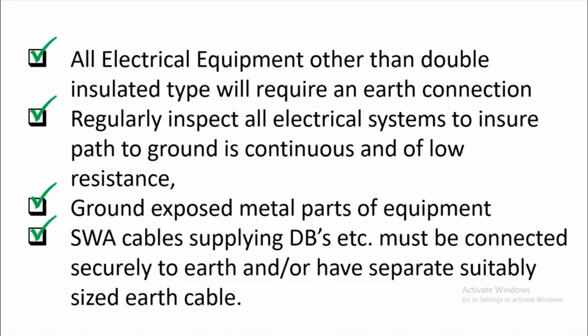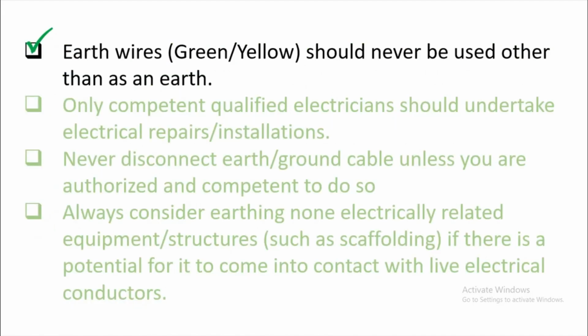All the exposed metal parts of the equipment should also be earthed or connected to the earth connections. Steel wire armored cables supplying distribution boards etc. must be connected securely to earth and/or have a separate suitably sized earth cable. So even if these are armored cables, they should be connected to the earth. Earth wires, green and yellow, should never be used other than as an earth. So remember, there is a color coding on electrical cables. You cannot use the green or green and yellow for any other purpose other than for the earth connections.